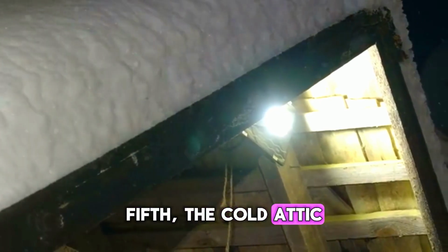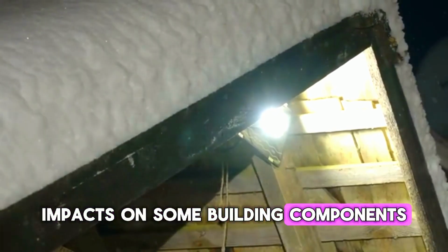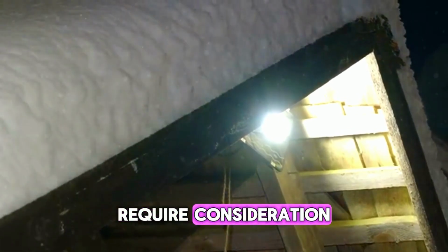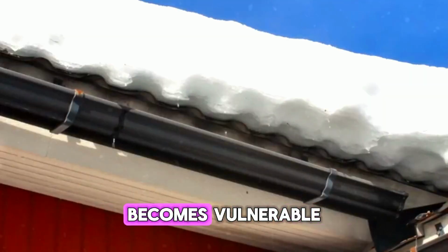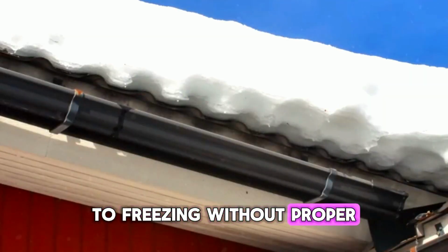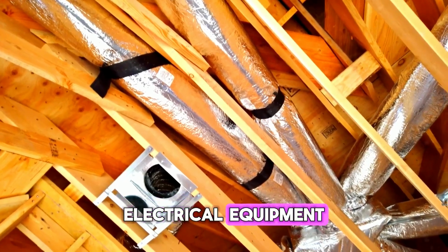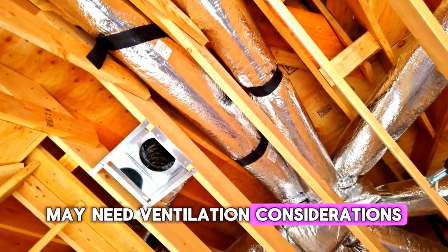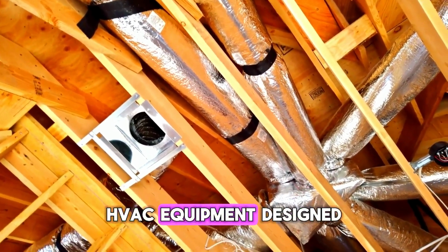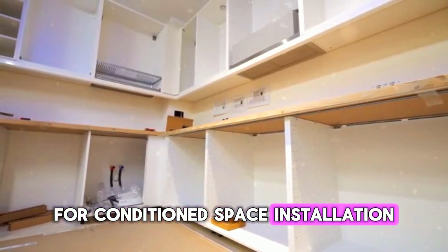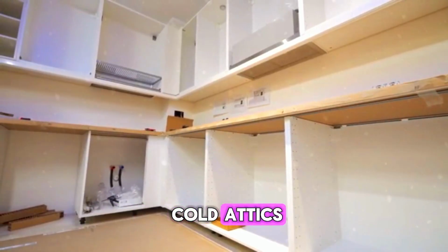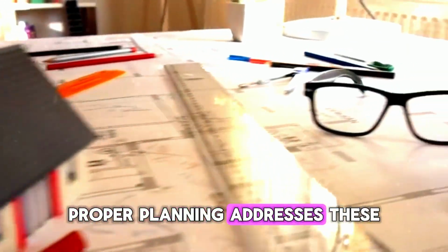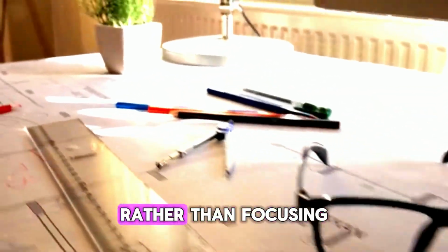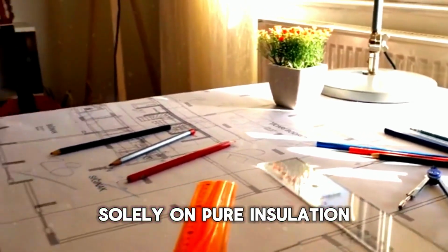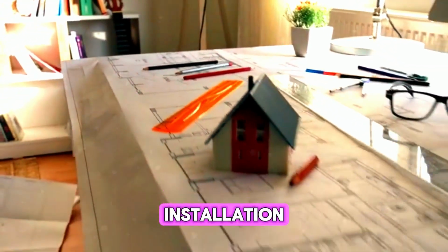Fifth, the cold attic impacts on some building components require consideration. Piping in cold attic spaces becomes vulnerable to freezing without proper protection. Electrical equipment may need ventilation considerations. HVAC equipment designed for conditioned space installation may face issues in cold attics. Proper planning addresses these secondary considerations rather than focusing solely on pure insulation installation.